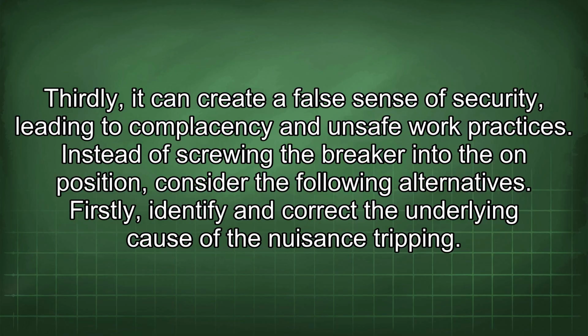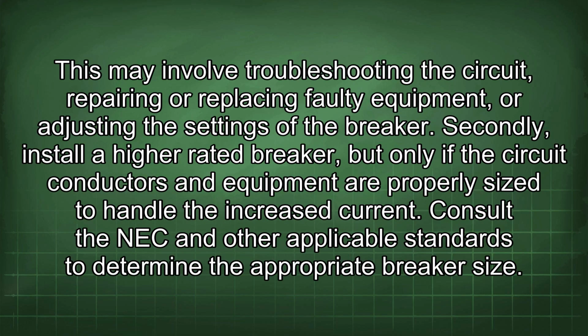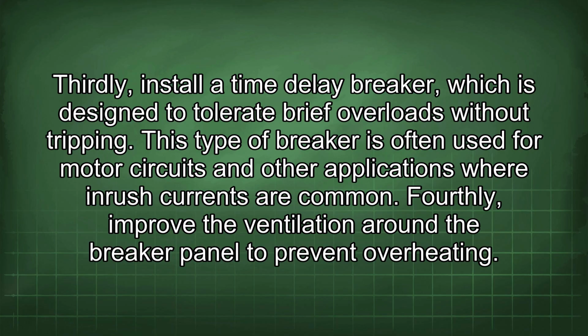Instead of screwing the breaker into the on position, consider the following alternatives. Firstly, identify and correct the underlying cause of the nuisance tripping. This may involve troubleshooting the circuit, repairing or replacing faulty equipment, or adjusting the settings of the breaker. Secondly, install a higher rated breaker, but only if the circuit conductors and equipment are properly sized to handle the increased current. Consult the NEC and other applicable standards to determine the appropriate breaker size. Thirdly, install a time delay breaker, which is designed to tolerate brief overloads without tripping. This type of breaker is often used for motor circuits and other applications where inrush currents are common.